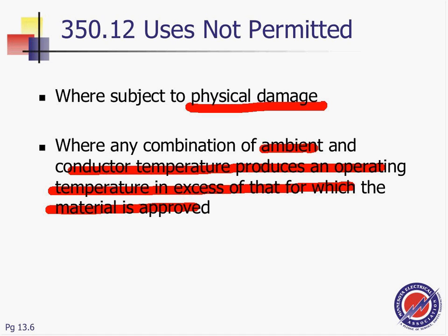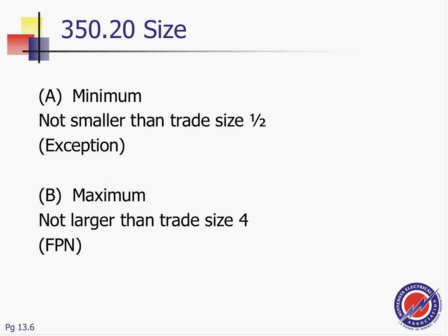Remember this, guys, it's all the time. If you have a non-metallic conduit, they always tell you you cannot put a conductor inside non-metallic conduit or anything that's non-metallic that will exceed the operating rated temperature of that non-metallic material. So especially for non-metallic. Metallic is not an issue. And since this one has a non-metallic jacket, the same rule applies to it. So, the temperature of the install. Okay, this is no problem.